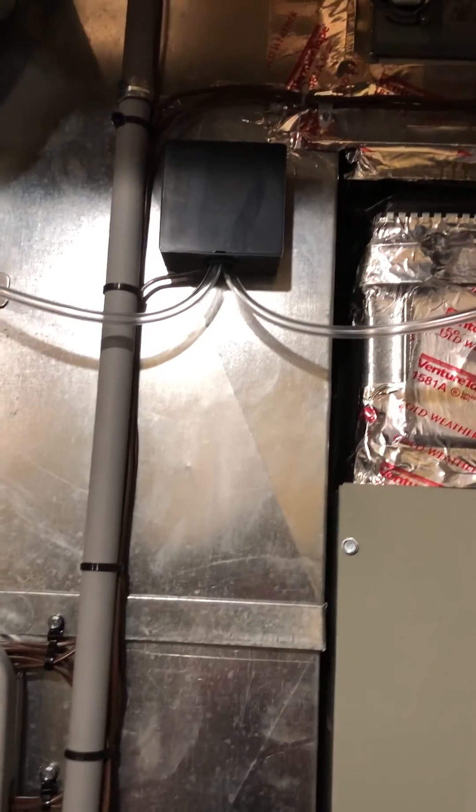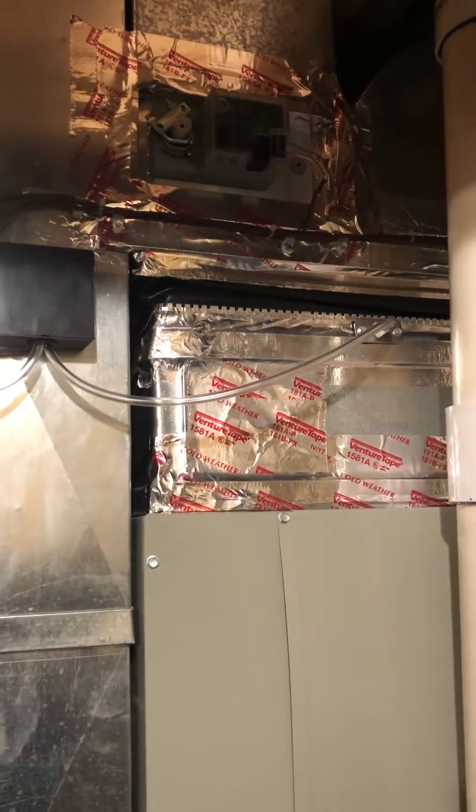This system is pretty cool. You use the pressure sensor here, and what it will do is max out and run up to a hundred percent. Then each zone will open and bleed, and it will determine how much capacity each zone can handle and adjust to that automatically.